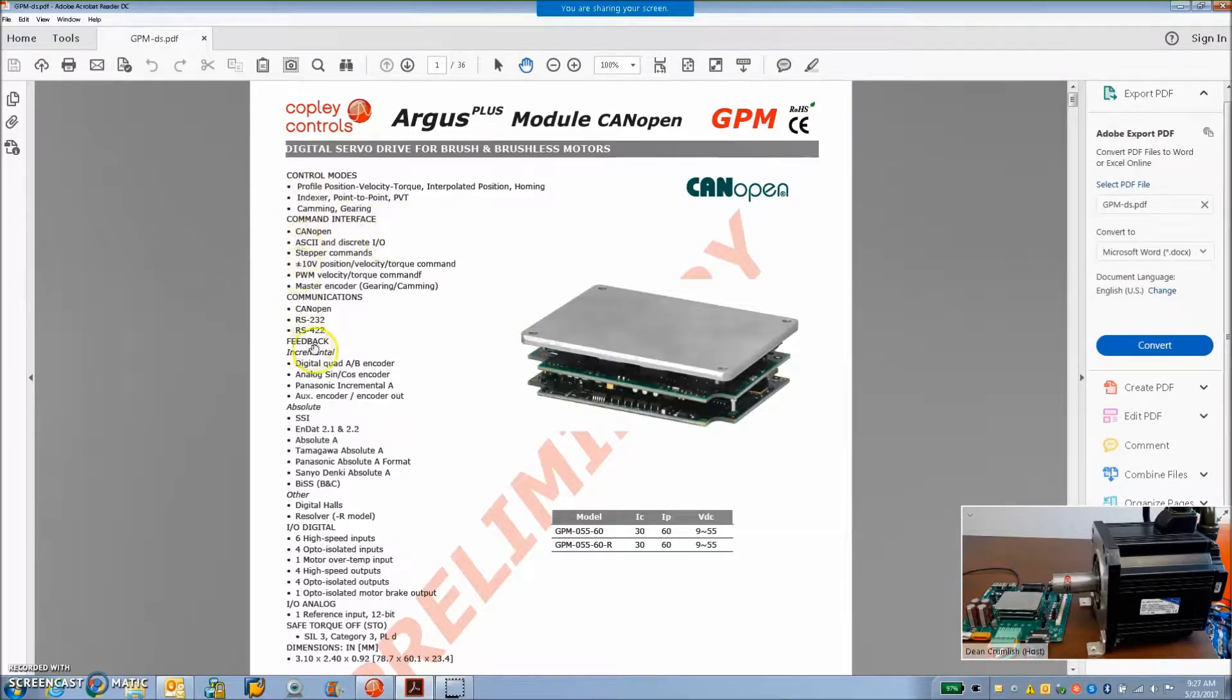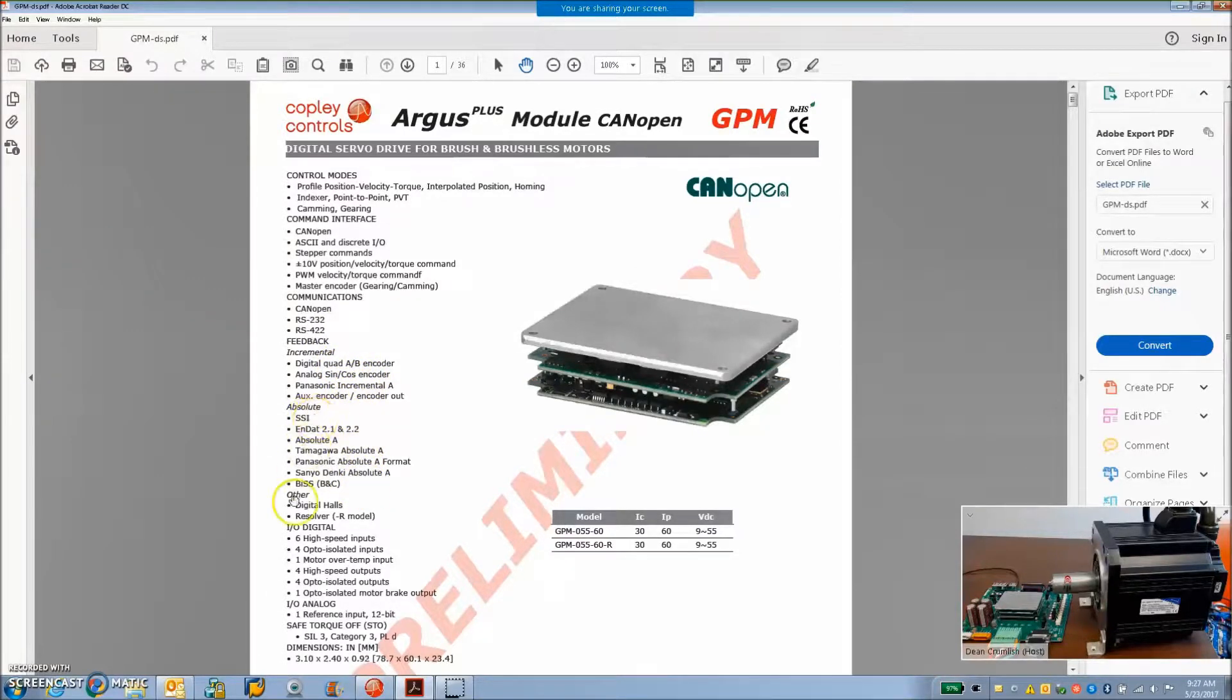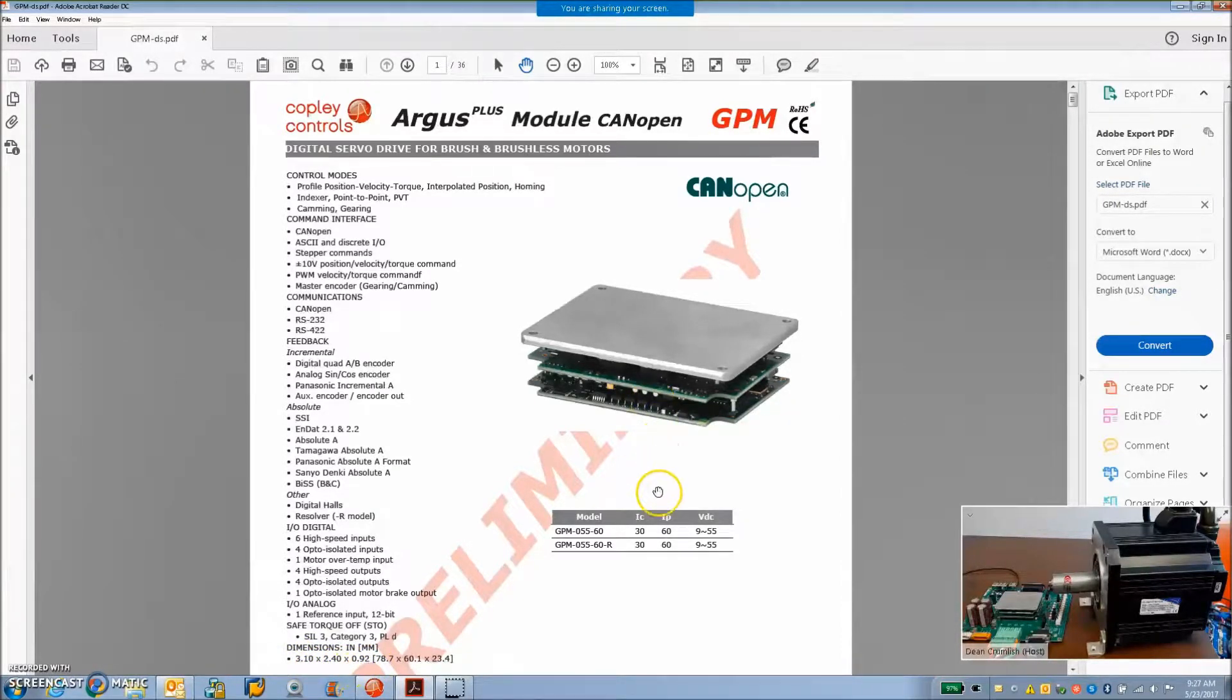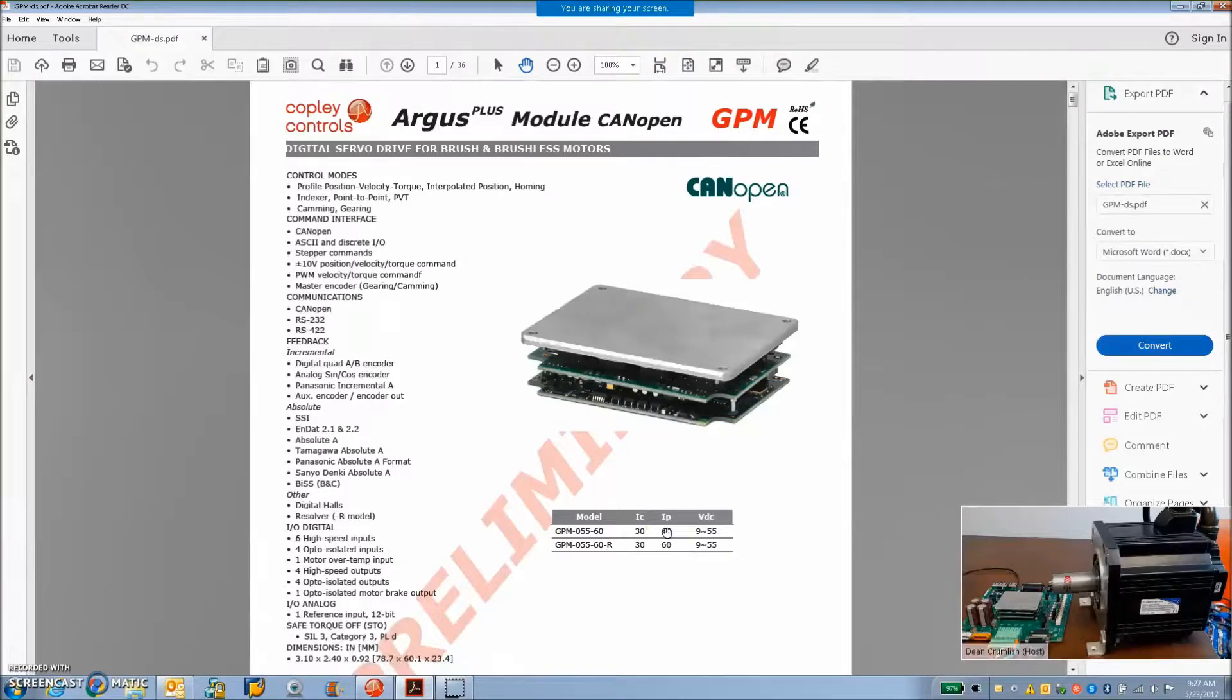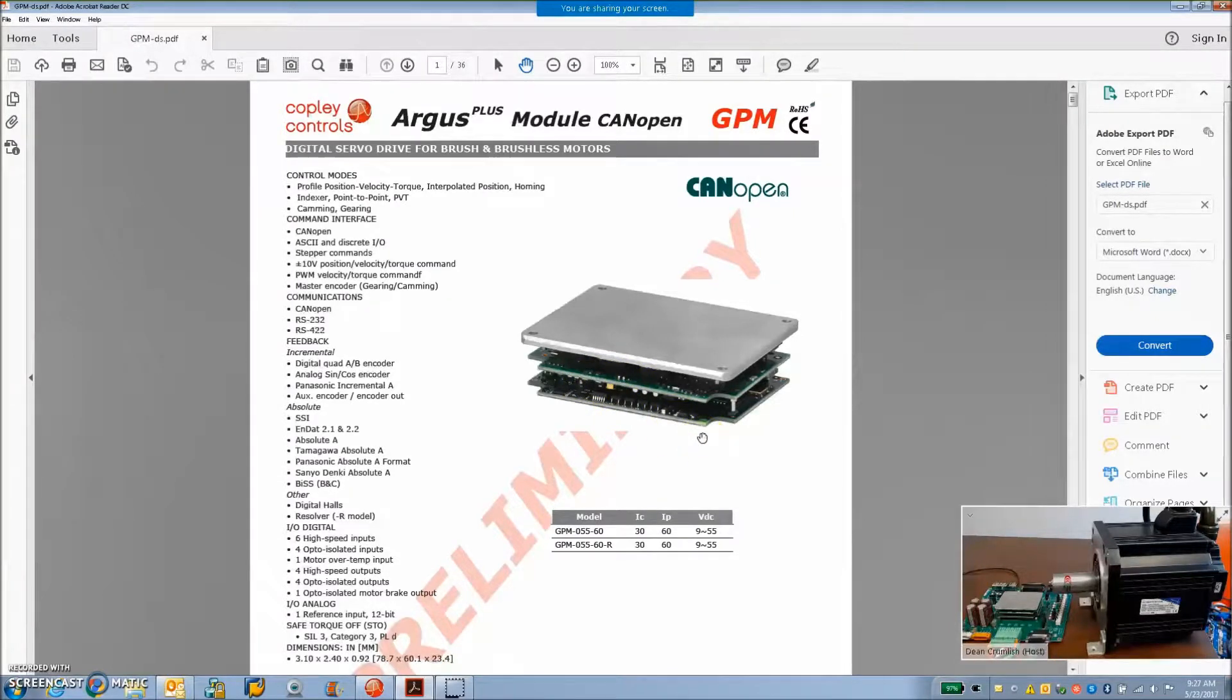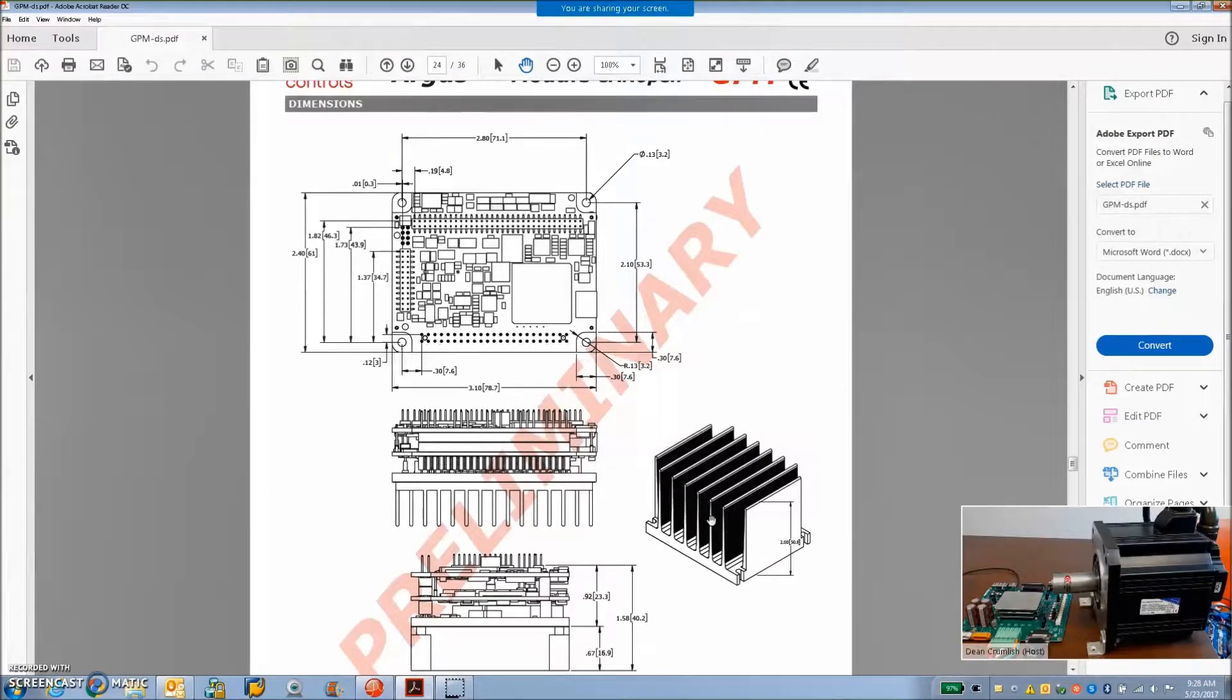But you can see it's a Plus drive. Some unique features about this is 422 option, that's standard, pretty popular in the rugged industry. You got your sine cosines and your incremental encoders and all the absolutes plus resolver. You get some I/O and it's a small package size: 3.1 inch by 2.4 by 0.9 inch. You know this is 60 amps for one second, 30 amps continuous from the connector with the pins. You could probably do a lot longer for peak current. I don't need it in this application, we're just going to spin this motor fast. But if you needed 60 amps for two seconds, I'm sure we could give it to you. You just probably have to solder the module pins into the board so that the pins can handle all the current. There is a heat sink option.